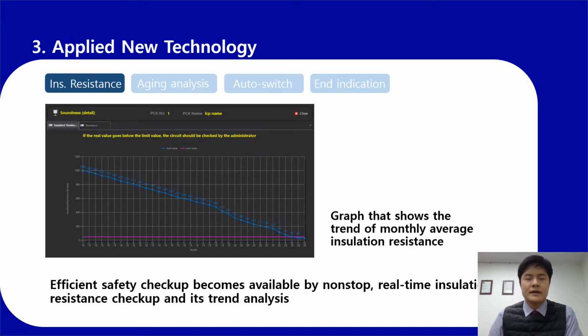In real time, the insulation resistance is saved as the average value of each month. With just one click, the manager can check the trend of the insulation resistance of the heating cable. It makes an effective safety checkup possible.